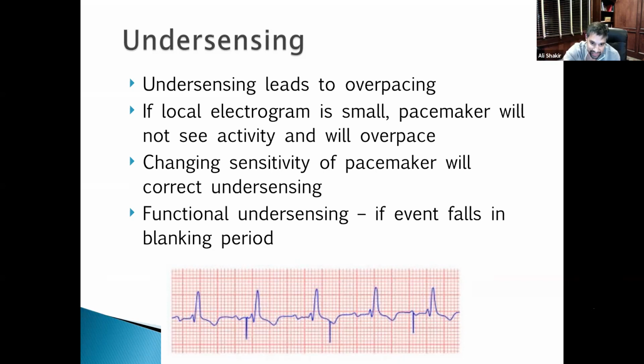So you have no sensing and no pacing, right? So it's undersensing. It's not even seeing any of those events, because the rate doesn't change. It's whatever is programmed, all 3 spikes happening at the same interval, whatever rate it is. And so the lead probably moved. Does that make sense? Yes. So here, when you have too many pacing spikes, remember that it's undersensing and it's not working. Yeah, that makes sense. Okay, keep going. And in this case, is it true non-capture? Is it functional non-capture?